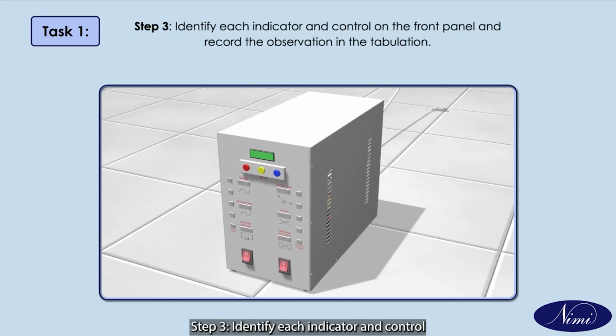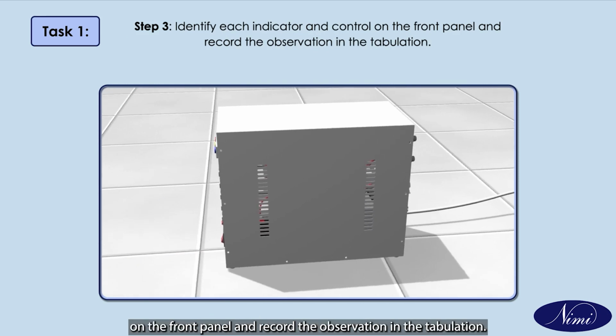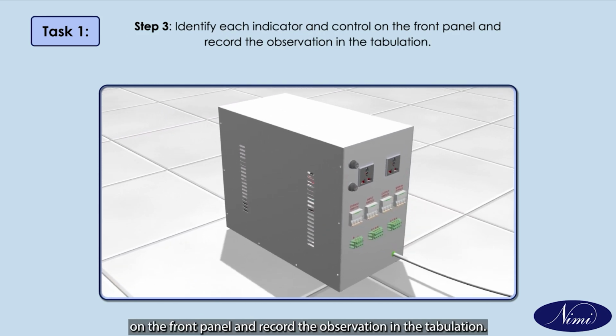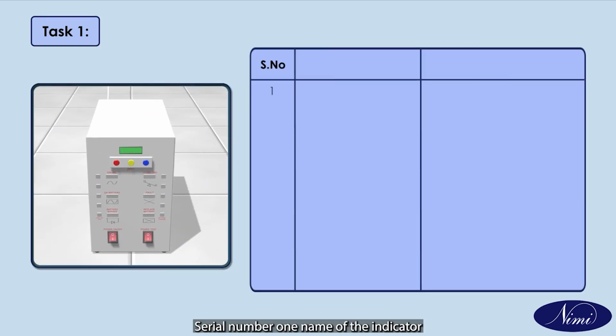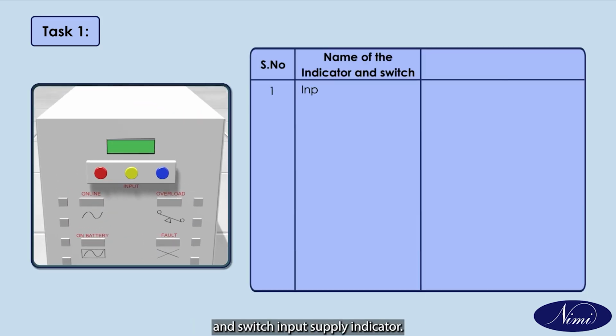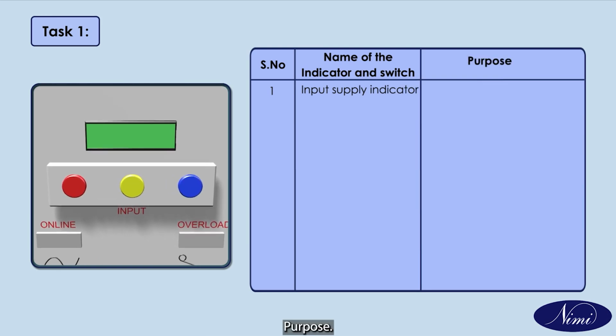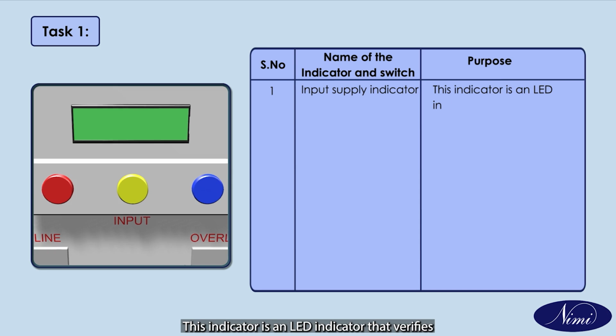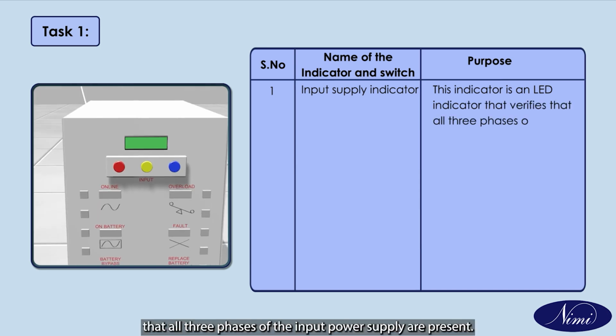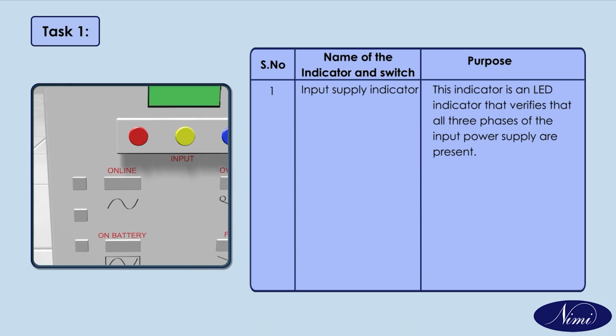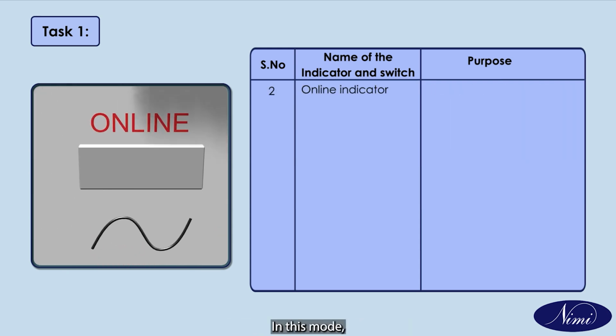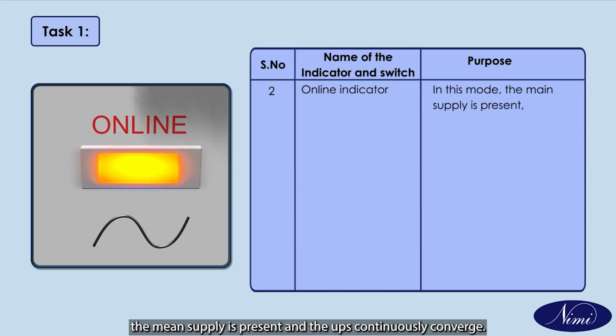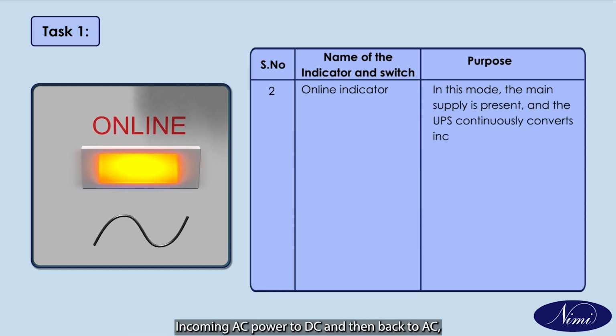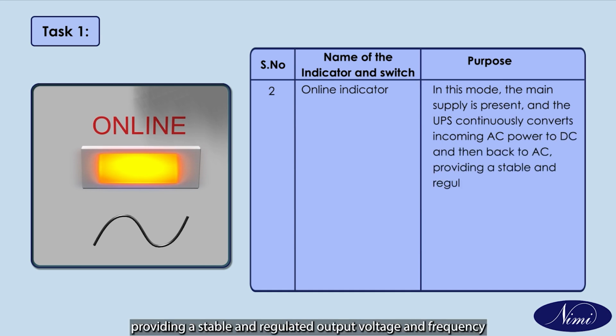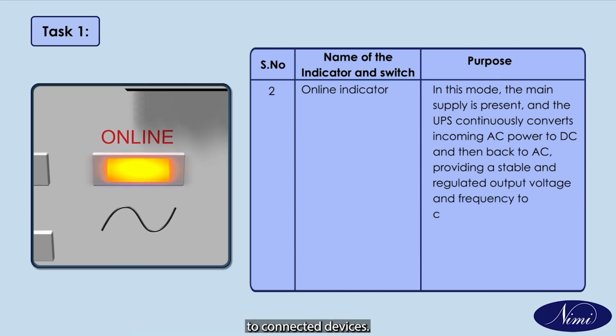Step 3. Identify each indicator and control on the front panel and record the observation in the tabulation. Serial number 1. Name of the indicator and switch: input supply indicator. Purpose: this indicator is an LED indicator that verifies that all 3 phases of the input power supply are present. Number 2. Online indicator. In this mode, the main supply is present and the UPS continuously converts incoming AC power to DC and then back to AC, providing a stable and regulated output voltage and frequency to connected devices.